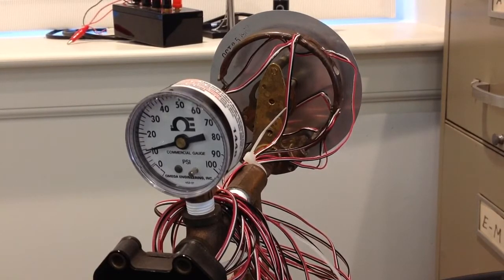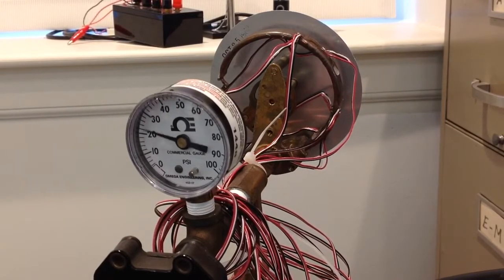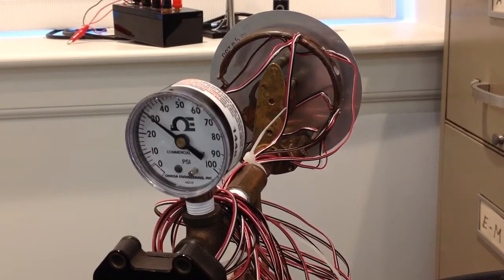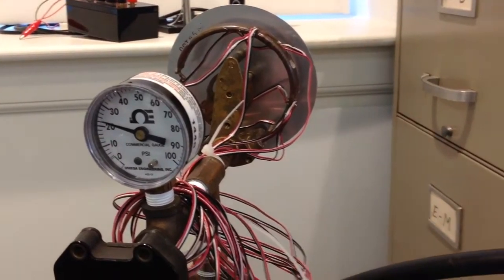So what you will be doing tomorrow is to basically set pressure at known locations. So for example, now I have around 12 psi inside, and now you will record data for calibration, and then increase pressure by small amounts, by 10 psi. And then record again, and you complete until 100 psi, okay? So that's the calibration. We will talk more about it tomorrow.